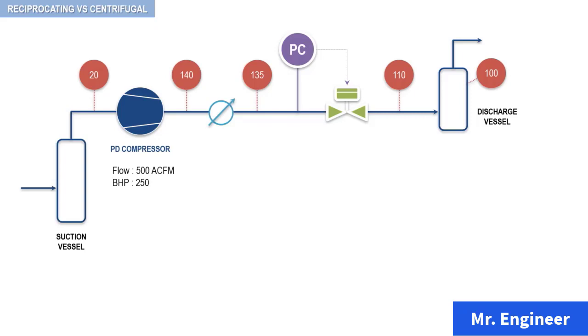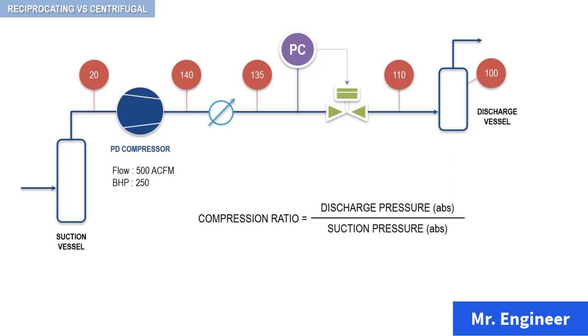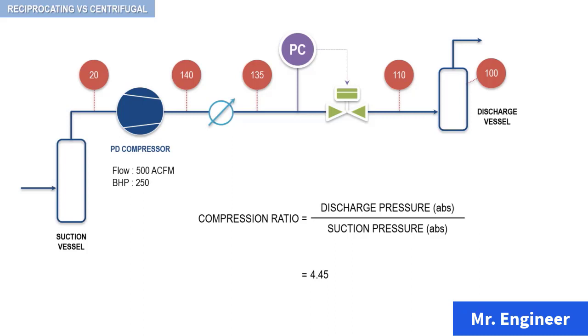The compression ratio, based on the suction and discharge pressures, is calculated as follows. It is equal to the discharge pressure expressed in absolute pressure, divided by the suction pressure of the compressor, also expressed in absolute pressure. So here, since all the readings are expressed in gauge pressure, we need to convert them into absolute pressure. The discharge pressure is equal to 140 psi plus 14.7, and the suction pressure is 20 psi plus 14.7. So the compression ratio is equal to 4.45.